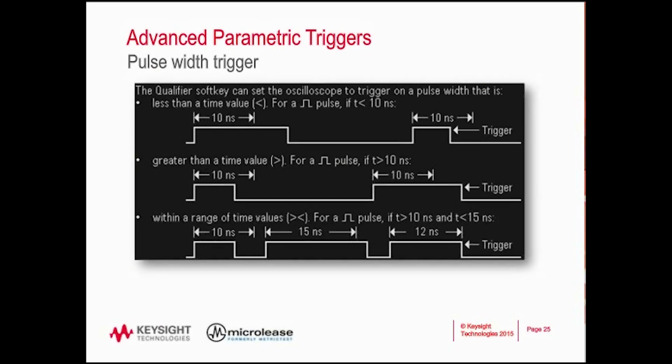What we're looking at here on the screen is actually a screenshot. Our oscilloscopes offer built-in help text that is often accompanied by diagrams and pictures for each of our advanced triggers, and actually many of our advanced measurements as well, which we'll discuss again in a later webcast later on this year. But it's pretty useful. You set up a trigger and you just press and hold on a button, and you're going to get built-in help.